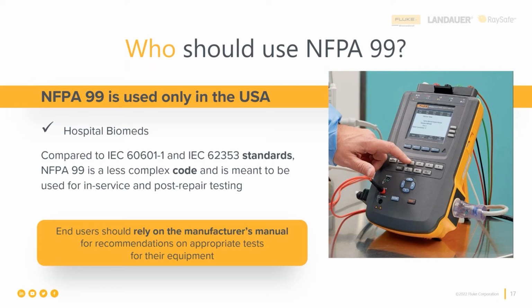So please don't fool yourselves about NFPA 99 being sufficient. You can argue that really the 62353 is what you should be doing. And that would satisfy requirements from the manufacturer, from the branded model-specific service manual test procedure, where the manufacturer will tell you which standard they need you to use. And by the way, in the United States, the part of the government that reimburses your hospital for the cost of care for Medicare and Medicaid patients is saying, we're happy with NFPA 99, but we're also happy with IEC 62353. So you're not going to get in trouble with auditors who are coming in, not even the fire marshal, if you're doing at least the NFPA 99, and the 62353 is not more burdensome in terms of how long it takes to do the test. Believe me, it's just not. So be careful, be thoughtful, and follow the right thing.